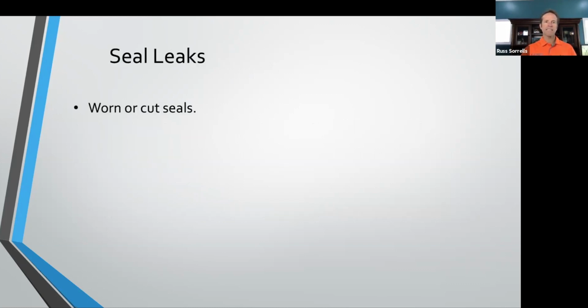All right, let's talk about seal leaks. The most common problems that I experience, and I'm sure Gordon, you can attest to this. The most common problem are seal leaks because the polyurethane seals that we would recommend that we use, or the O-rings that are being used, they wear out, they cut, they get debris on them and cause leaks. And this happens.